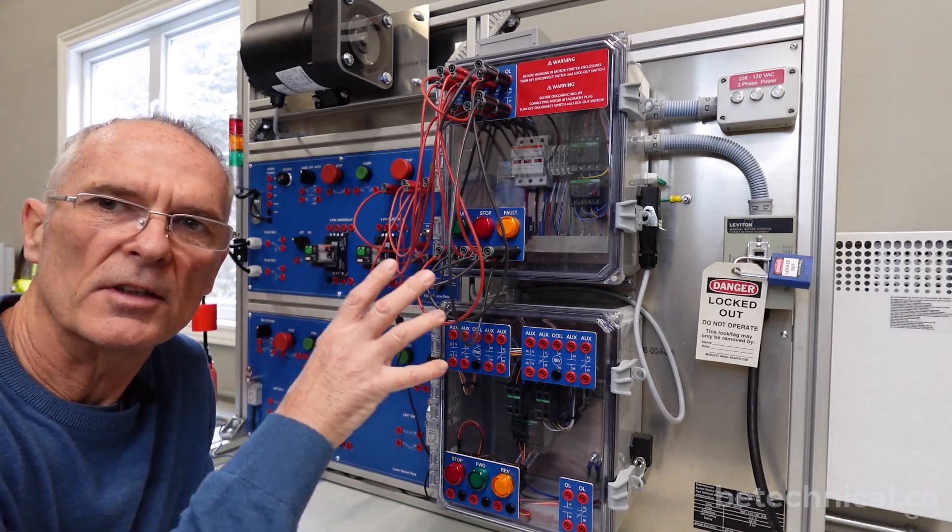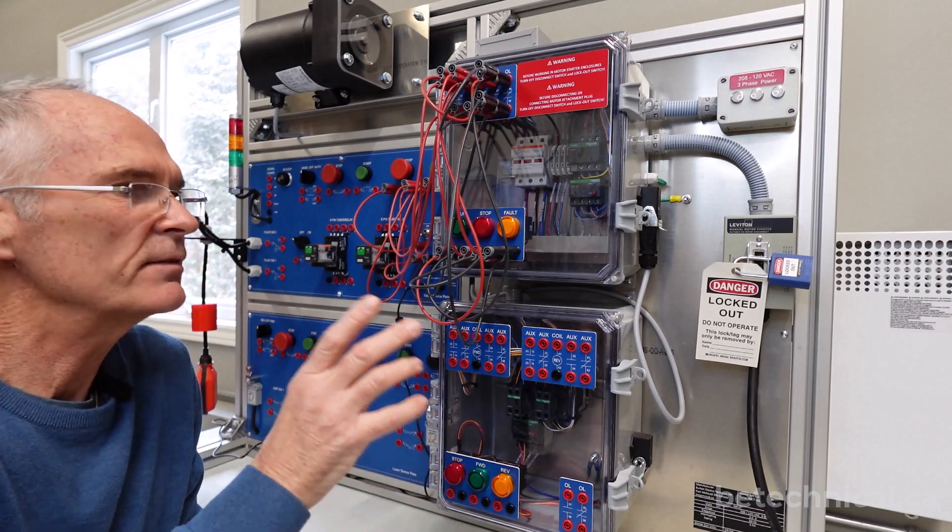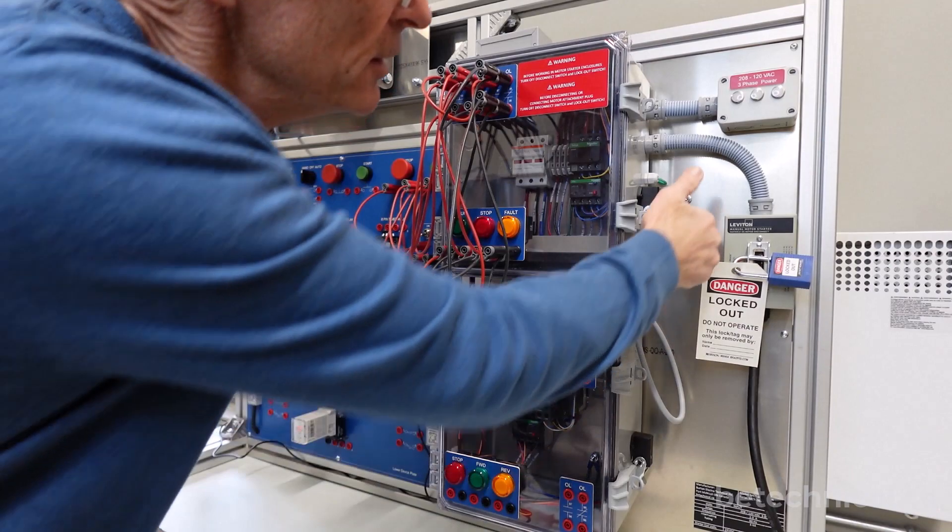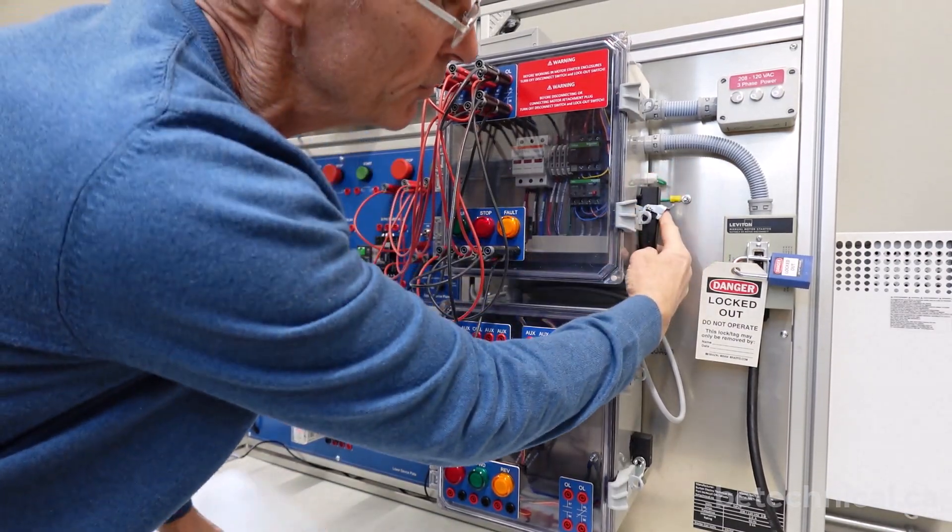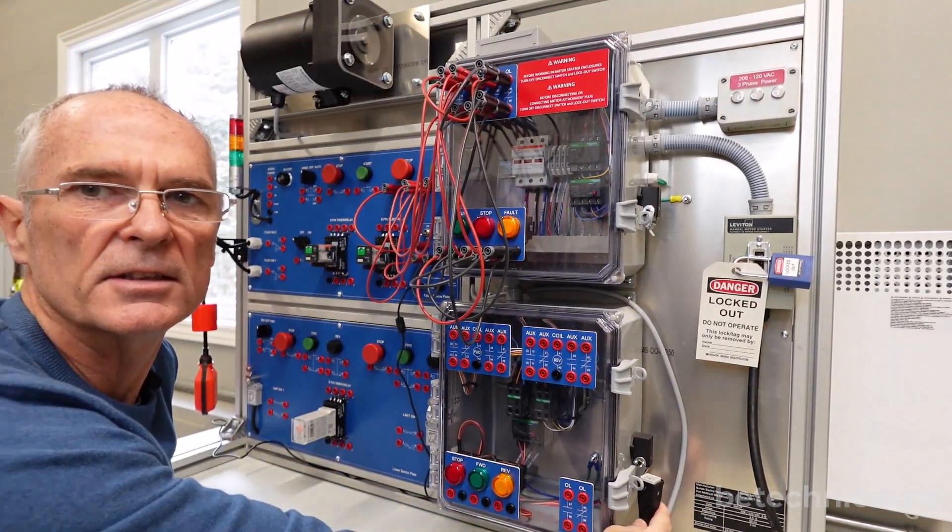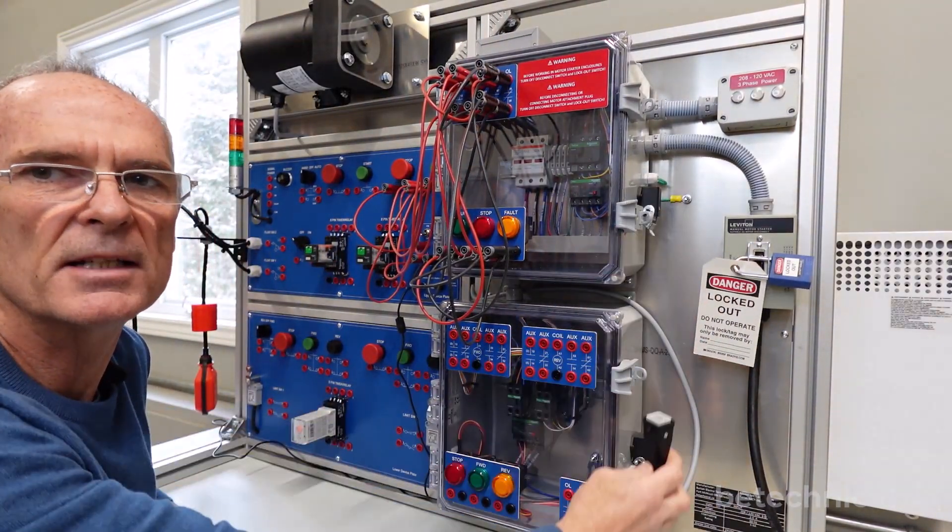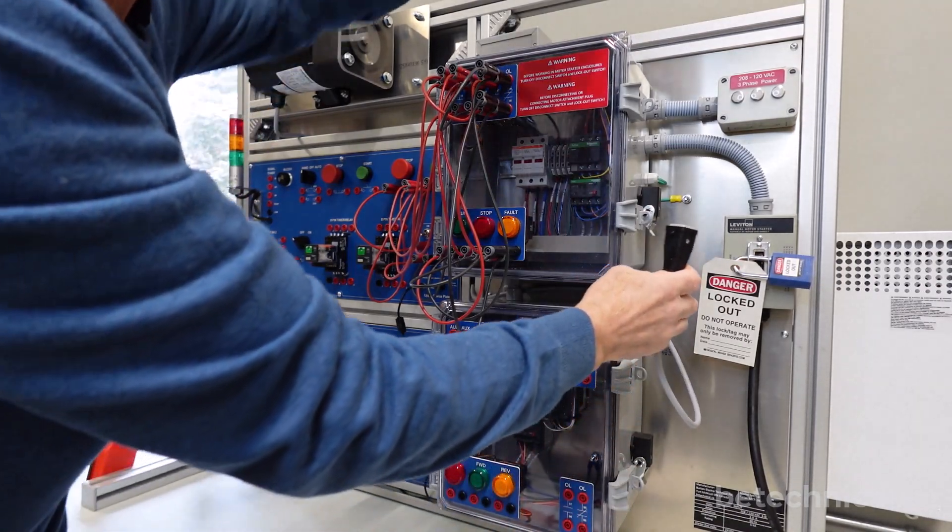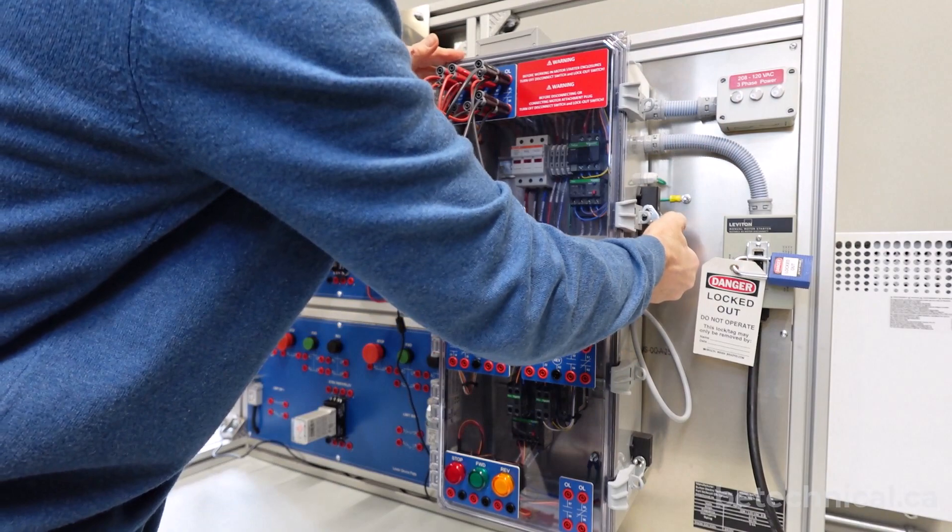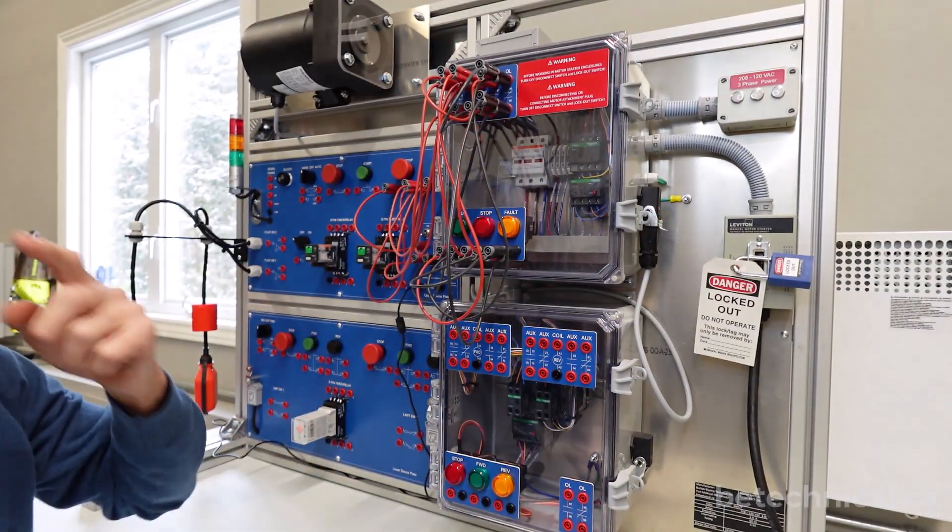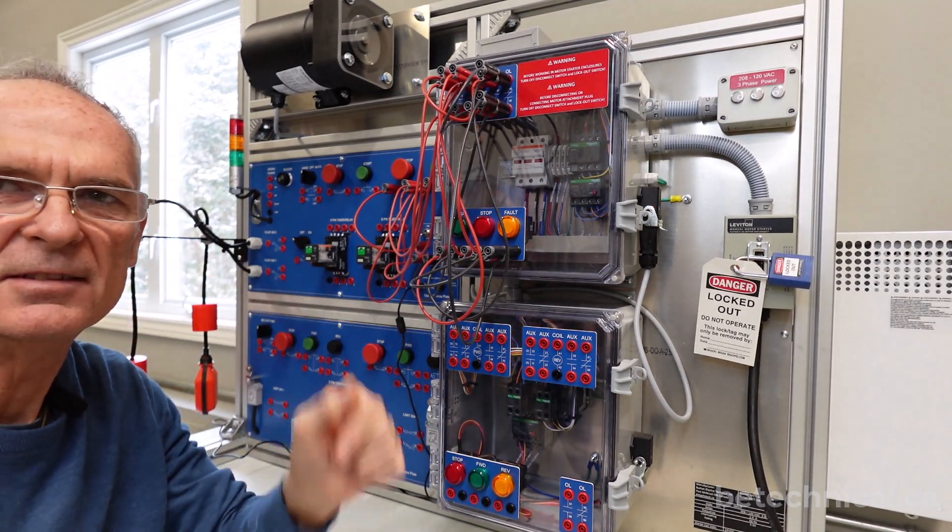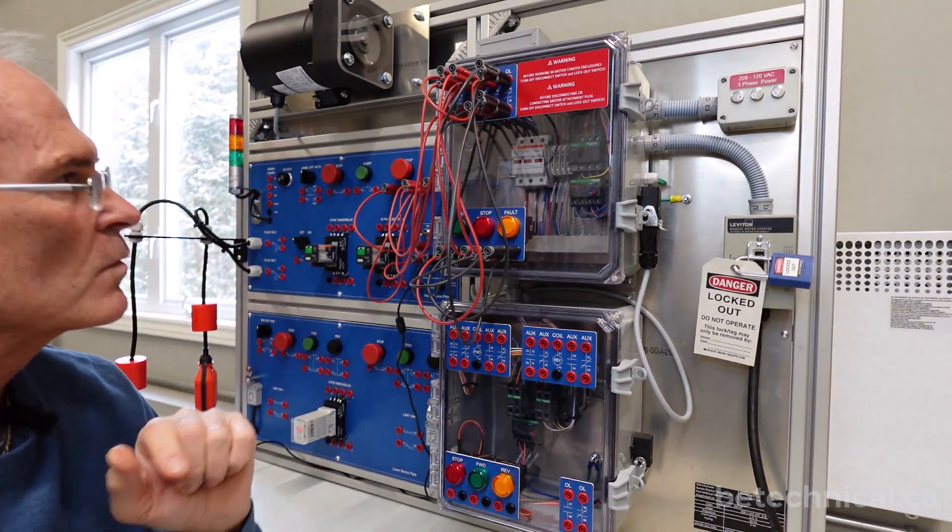When you're working with non-reversing and reversing projects, you have to switch between the two enclosures. You have to disconnect the motor from the non-reversing and connect it to the reversing and vice versa depending on which projects you're working on. So right now I have a project wired up for non-reversing, so I'm going to connect that. So I have the motor connected to the non-reversing. So that's something that they forget once in a while. They hit the start button and nothing happens.